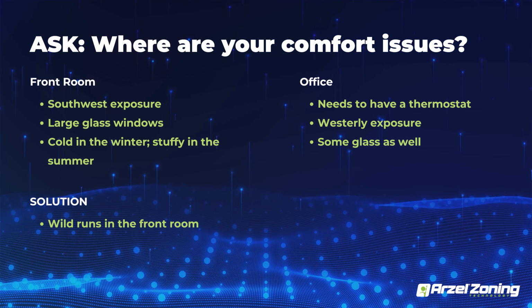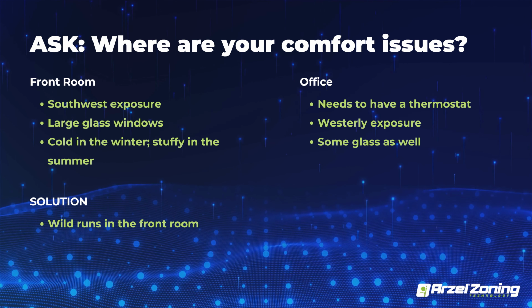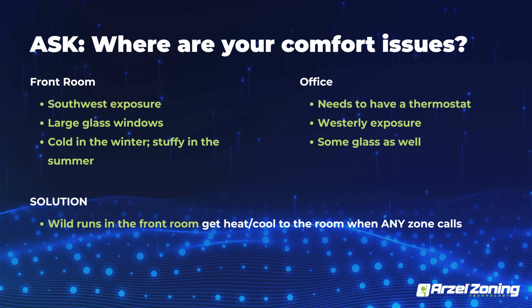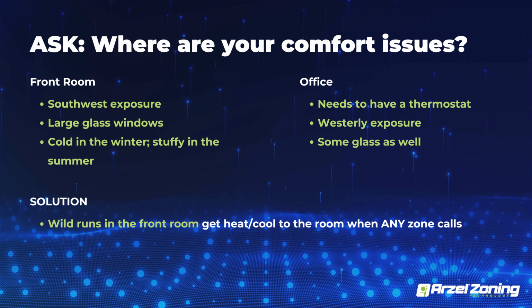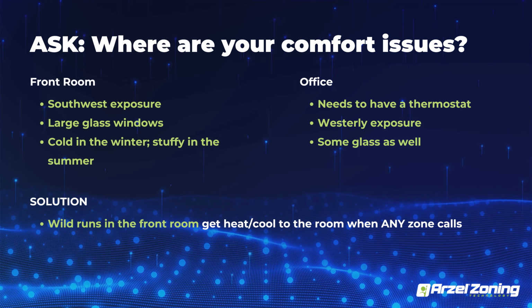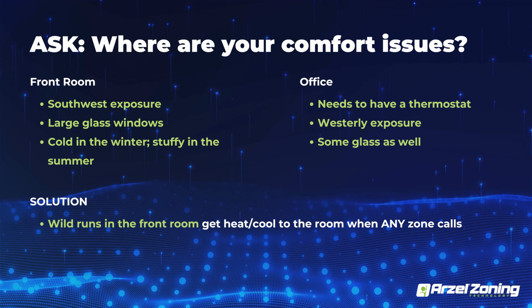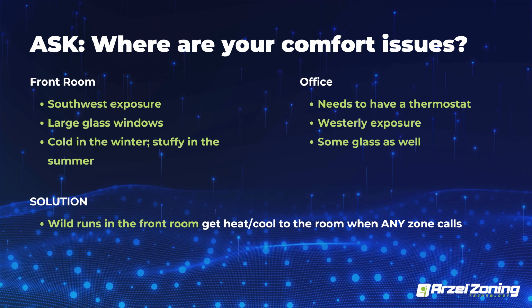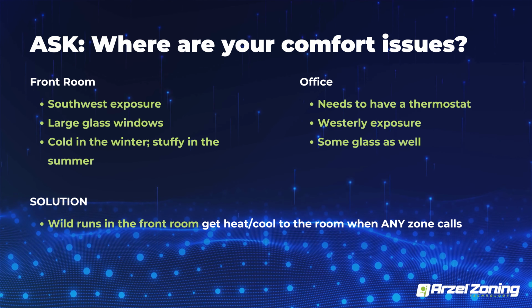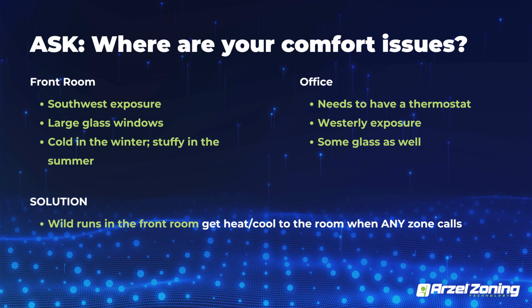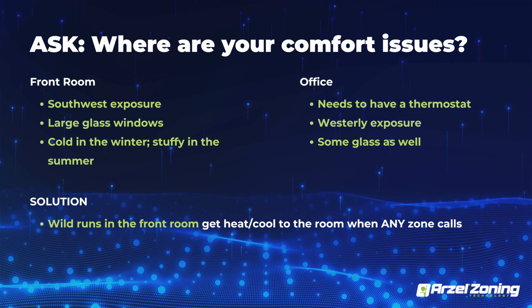When it called over there, the front foyer got heating. It got a blast of heating to take that load off. More importantly, when the husband went into his office, which by the way, I believe the first floor system was 4 tons and there was only one 6-inch run in his office. It wasn't a very big office.